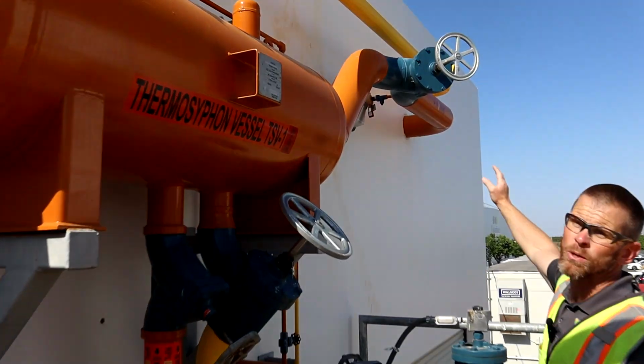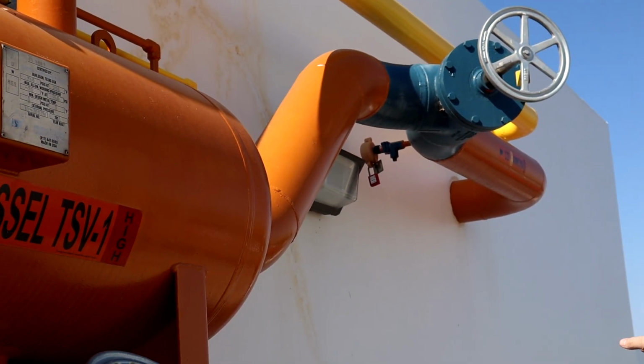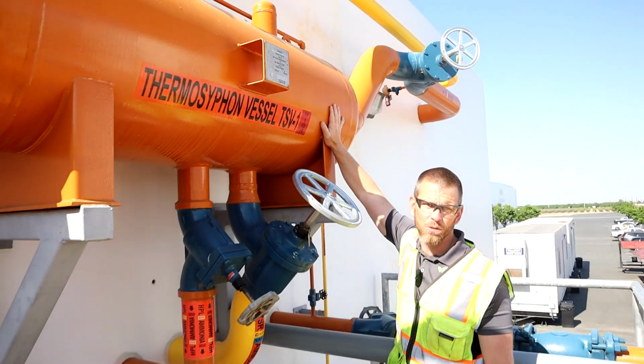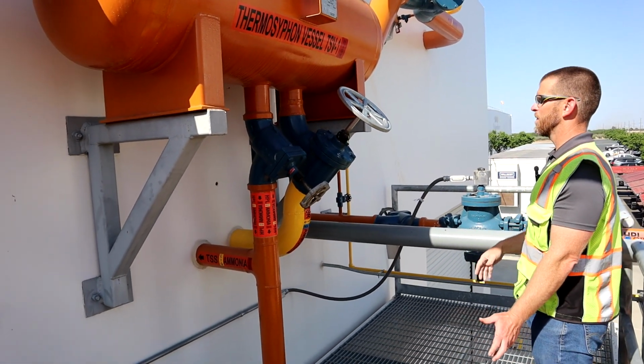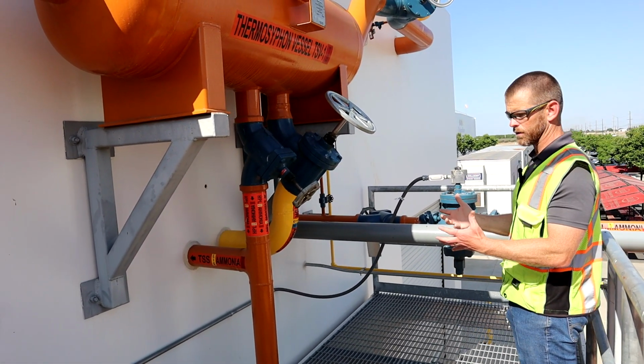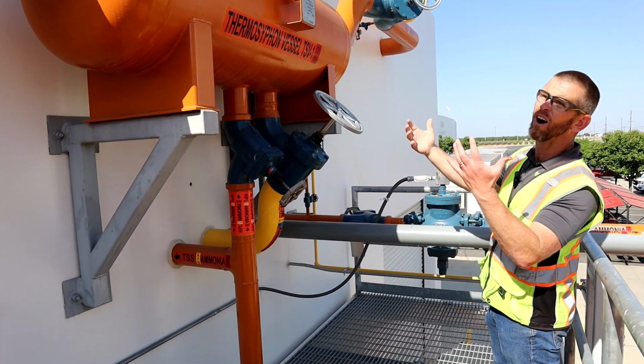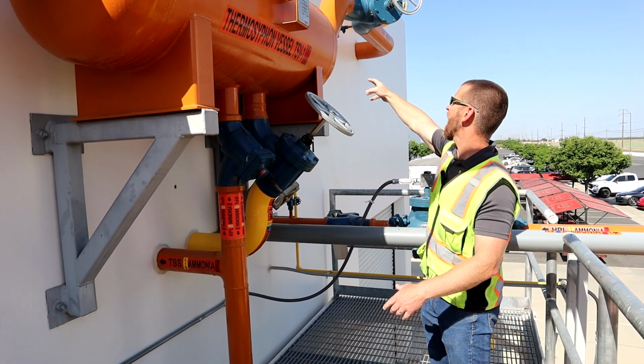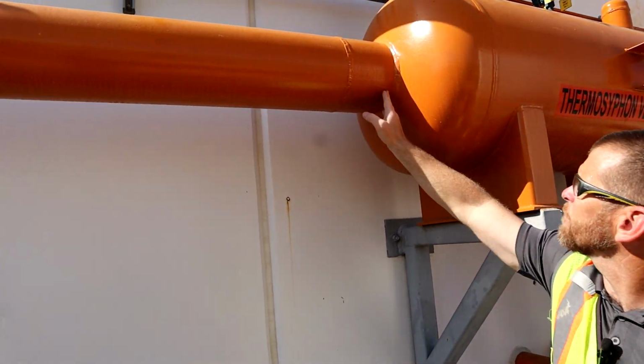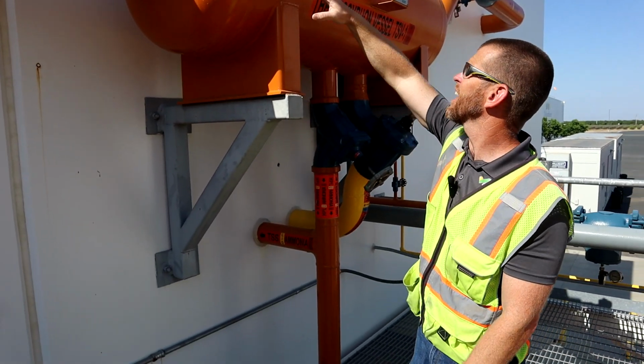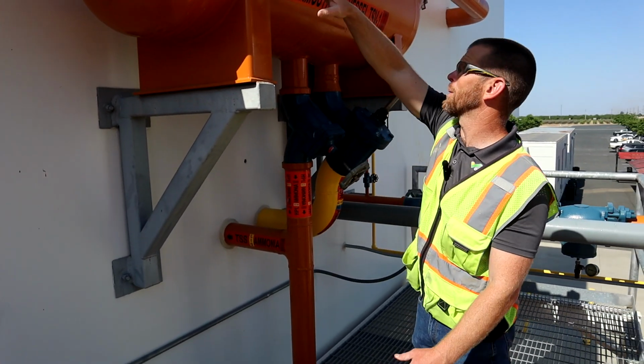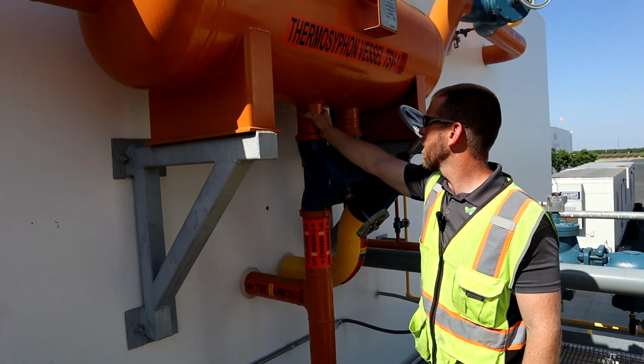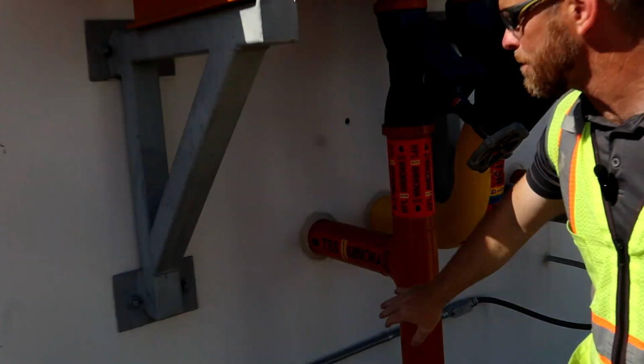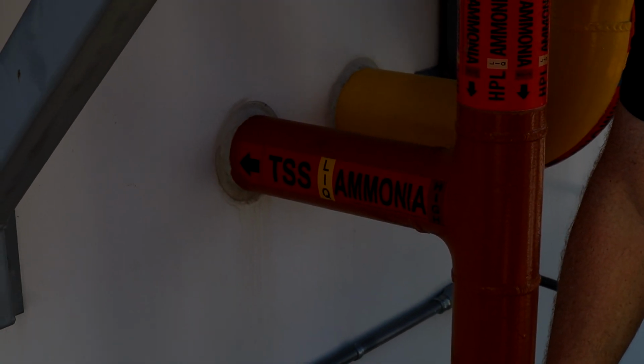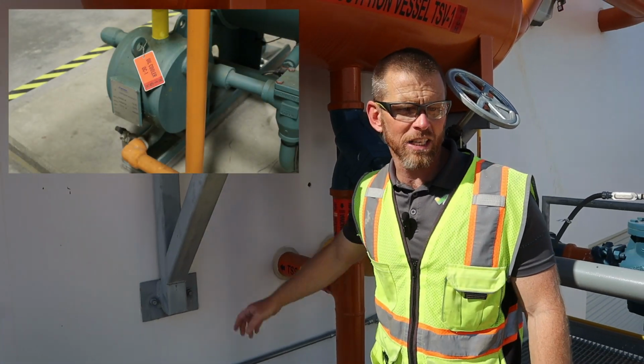So from the condensers, which you can't see from here, but through this orange pipe, the condenser drain line drains into this vessel. Now, this vessel does not have any float switch or level column on it, as you can see. And in fact, from this vessel, it drains about halfway up, it drains out and into our high pressure receiver. So in a sense, this is just an overflow vessel. But halfway up, there'll be a liquid supply halfway across this vessel so that we have a constant supply of liquid into this pipe that's labeled TSS, or thermosyphon supply. This is what's going to our oil coolers inside the machine room.